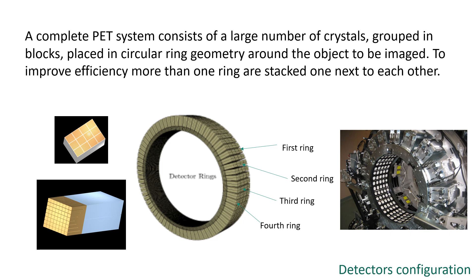A complete PET system consists of a large number of crystals grouped in blocks placed in a circular ring geometry around the patient to be imaged. To improve efficiency, more than one ring are stacked next to each other, and the total axial field of view depends on the number of detector rings in the scanner. The scanner model can be scaled with different numbers of rings.